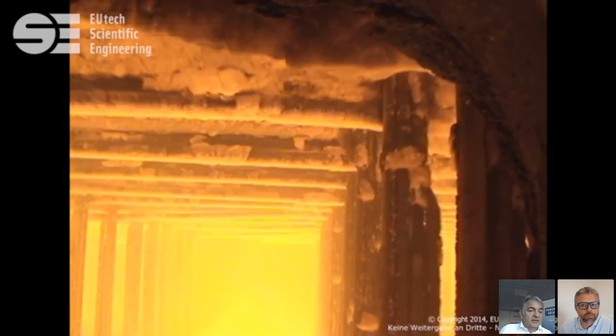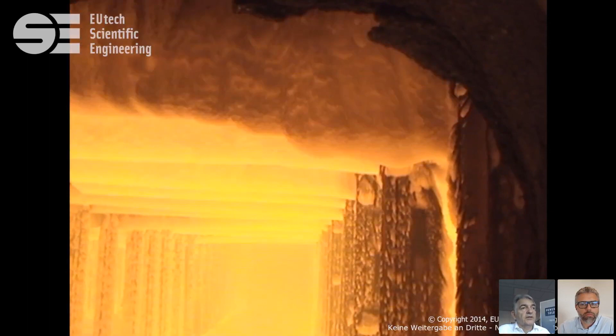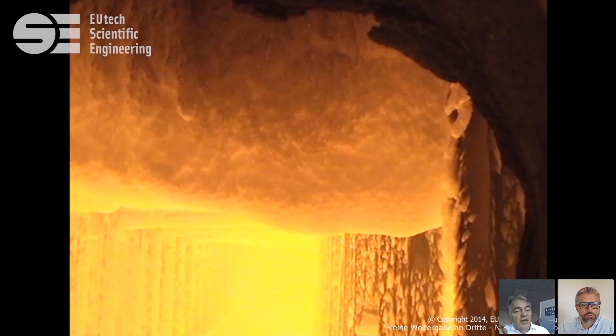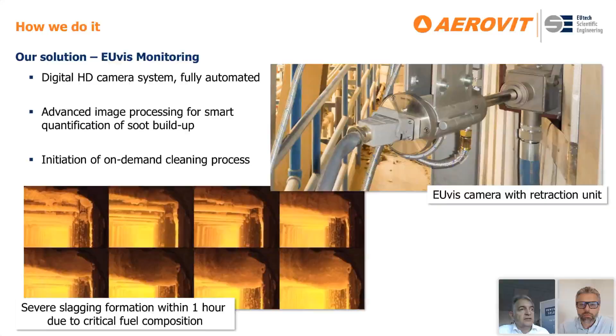This is the build-up of a heat exchanger by sooting, and this is a time lapse of 1 hour, and the build-up is more than half a meter. So it's almost 1 meter at the end, and you see how quickly it is happening. And when you look at the image, you can imagine if this falls down uncontrolled, you will damage definitely your furnace bottom, and at the other side, of course, you lower the heat efficiency, the heat transfer efficiency.